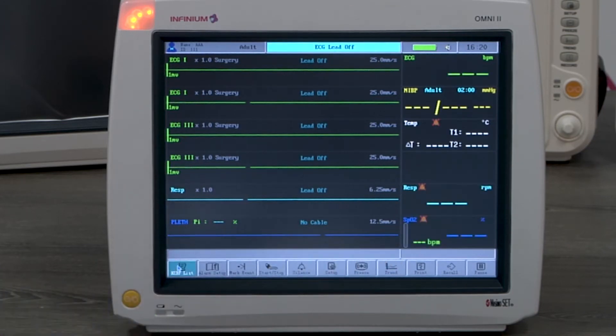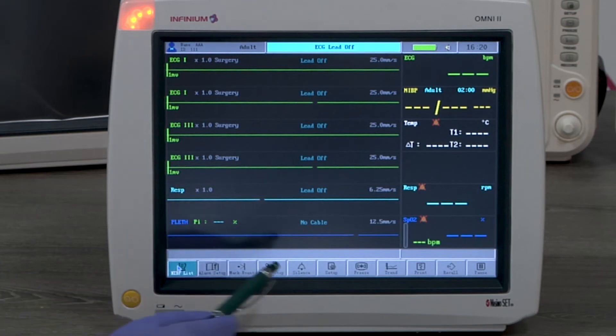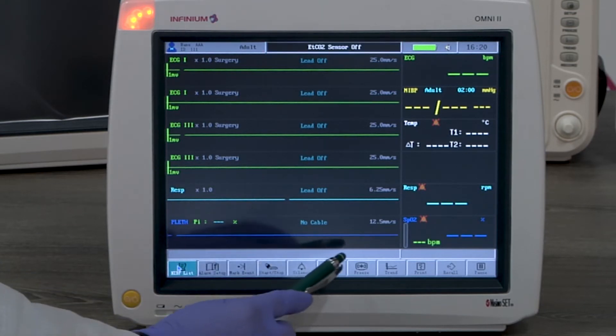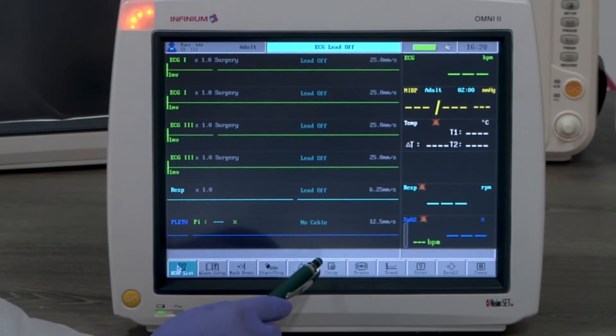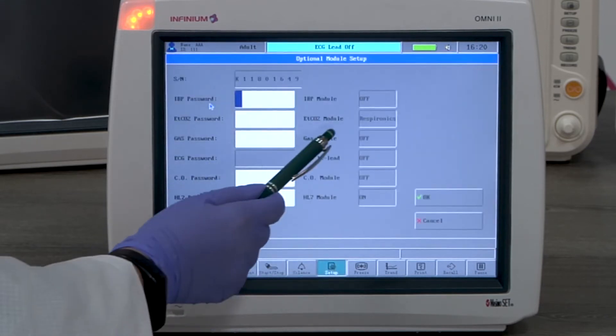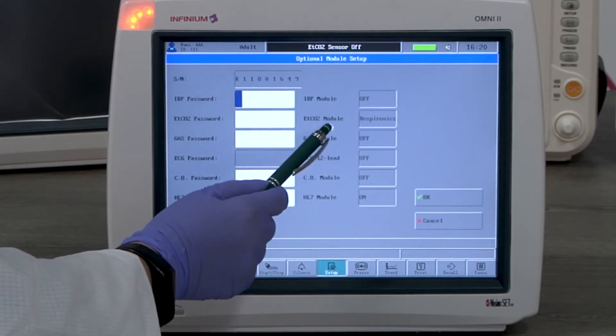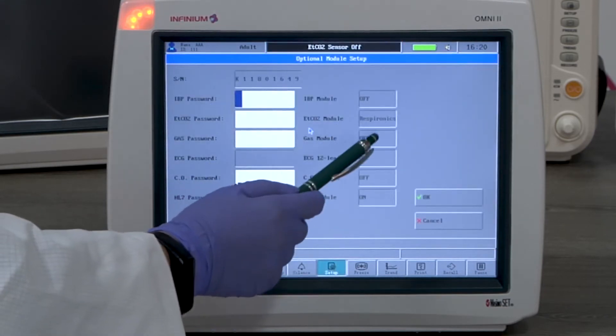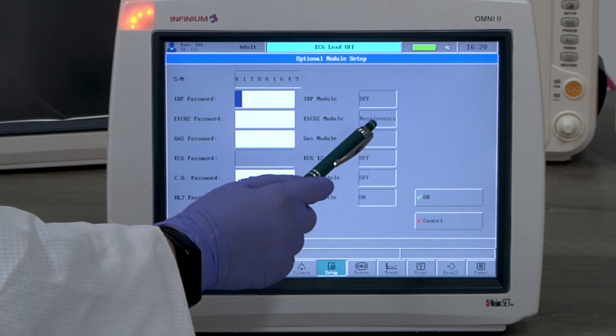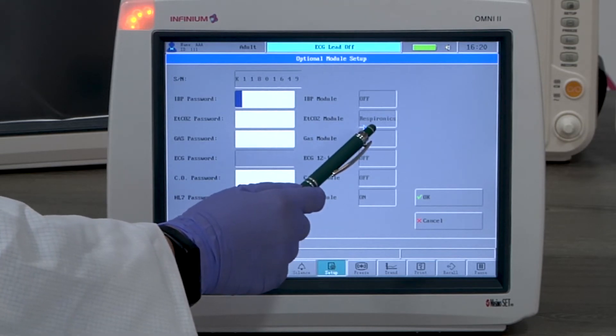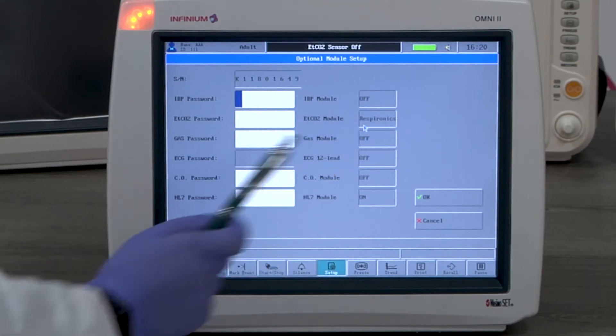Now let's look at ETCO2 monitoring. ETCO2 is an upgradeable feature. Its default is off, as are all the options. When it's unlocked, you'll see a CO2 type selected here. This will be either Respironics or Phase-in.